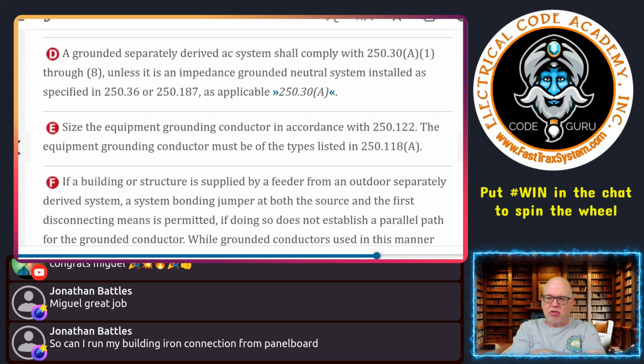The only difference is you do have what's called impedance grounded neutral systems, which make its connection virtually to Earth through a high impedance, an impedance device. Okay, and those are called impedance grounded neutral systems. Okay, and if that's the case, they're installed a little differently, and typically between the grounding electrode conductor and the XO, there is an impedance device right there. Okay, that type of thing. And those are typically used on systems where they want the system to be maintained and run longer and not have an issue with it. Okay, let's see here.